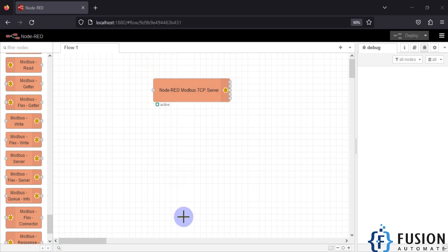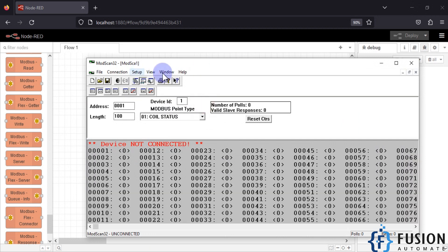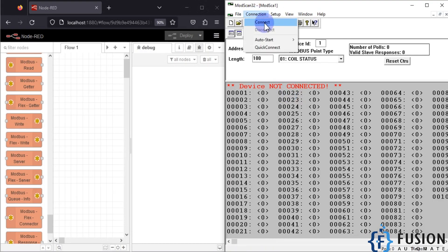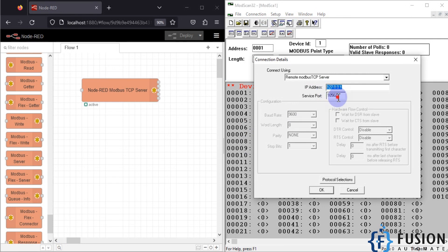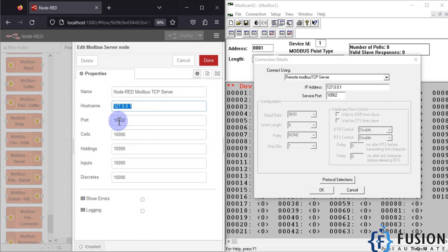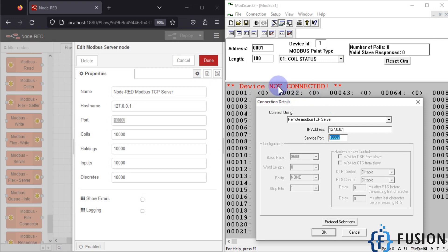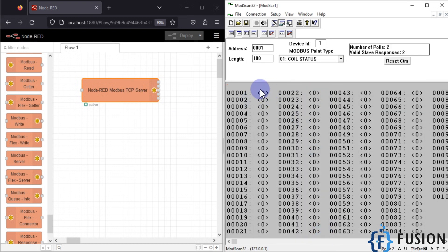Now we open our Modbus client application — in my case, ModScan. We want to connect to this Modbus TCP server, so we go to Connection and click Connect. Enter the IP address 127.0.0.1 and port 10502 copied from the Node-RED server configuration, then press OK. Before pressing OK the device showed as not connected, but after pressing OK the warning vanishes and ModScan is successfully connected to the Node-RED Modbus TCP server.